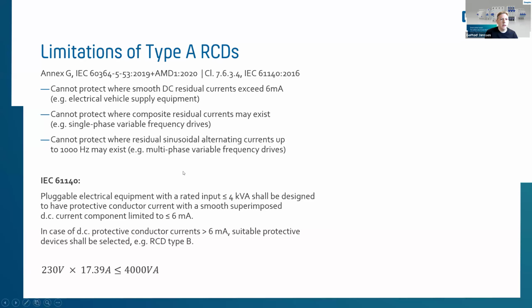And additionally to that, as per the IEC 61140, pluggable equipment or electrical equipment with rated input of up to 4 kVA shall be designed to have protective conductor current with a smooth superimposed DC current component limited to those 6 milliamps. So the threshold should be equal or below 6 milliamp, because otherwise a type B should be used. If you take a socket with 16 amp load, for example, then you will go on to the threshold of this 4 kVA. So sockets with more than 16 amp loads would require not a type A, but meanwhile a type B. But for standard sockets, for example, a type A is the best solution on the market.